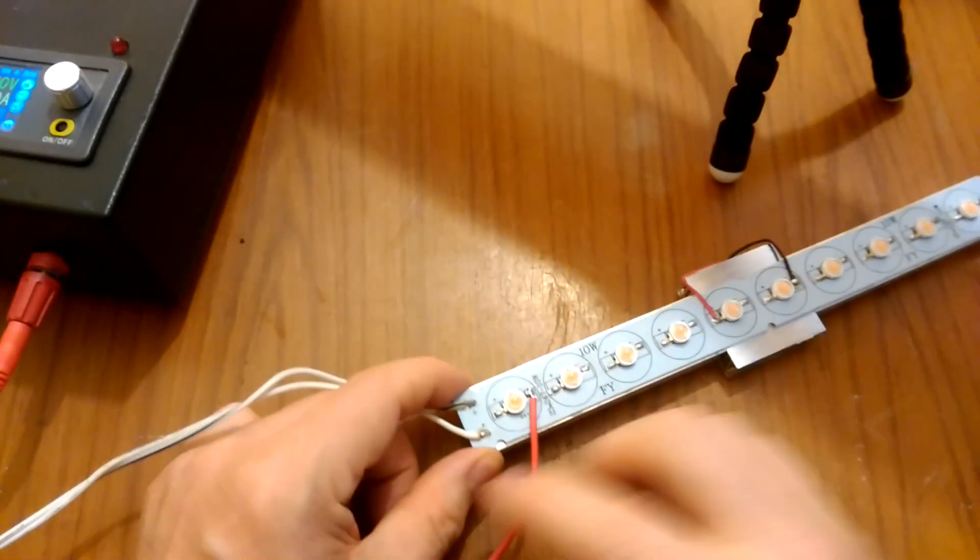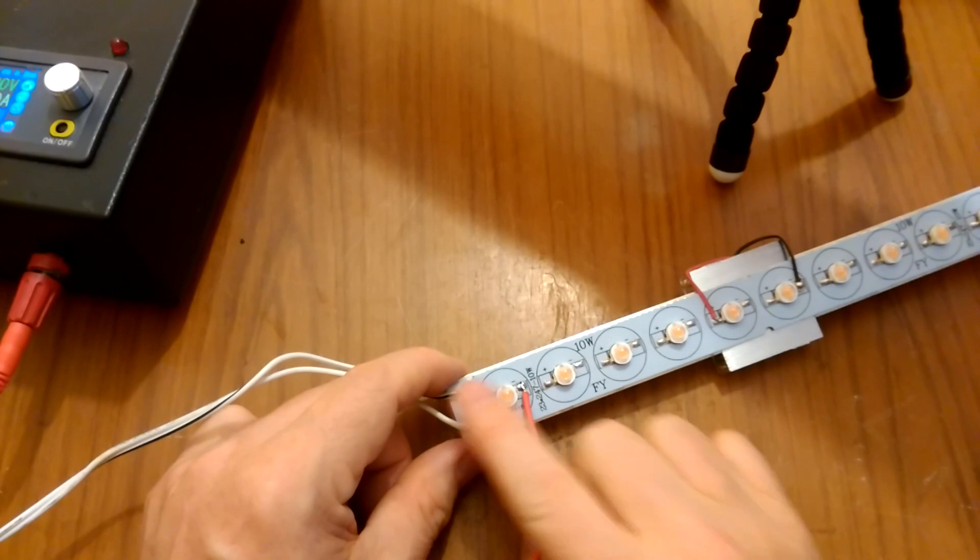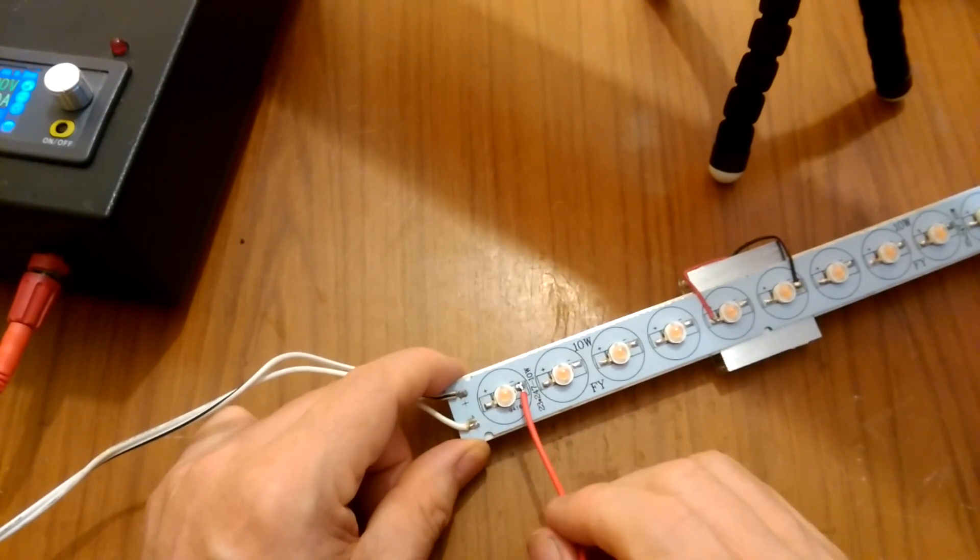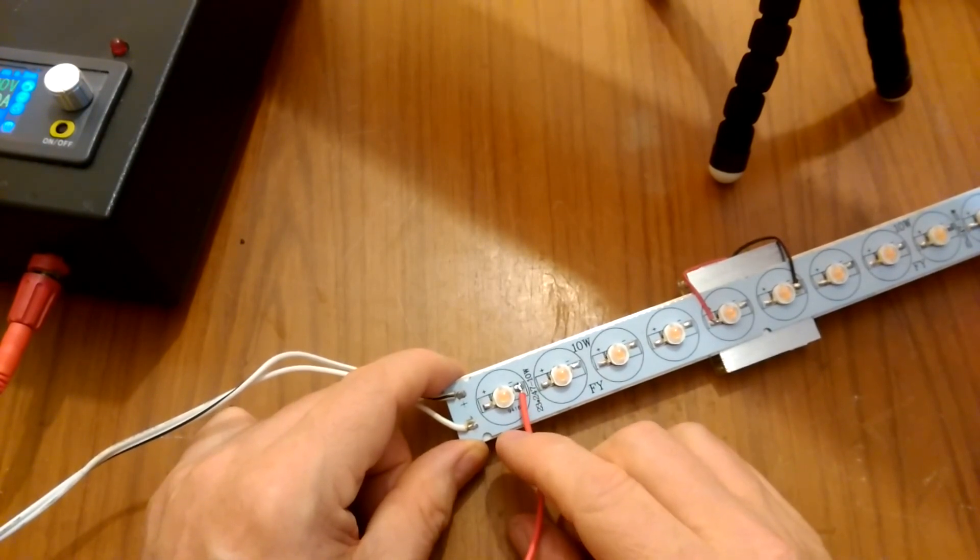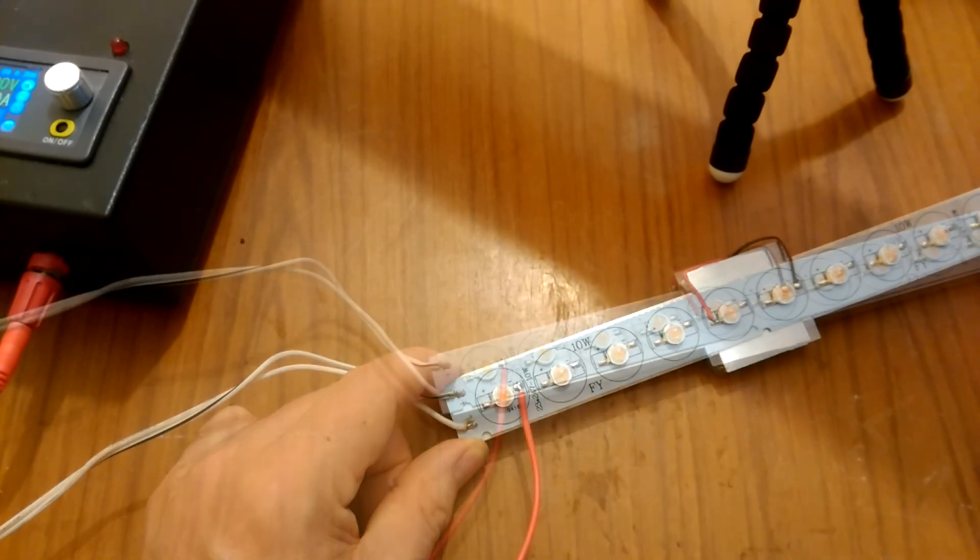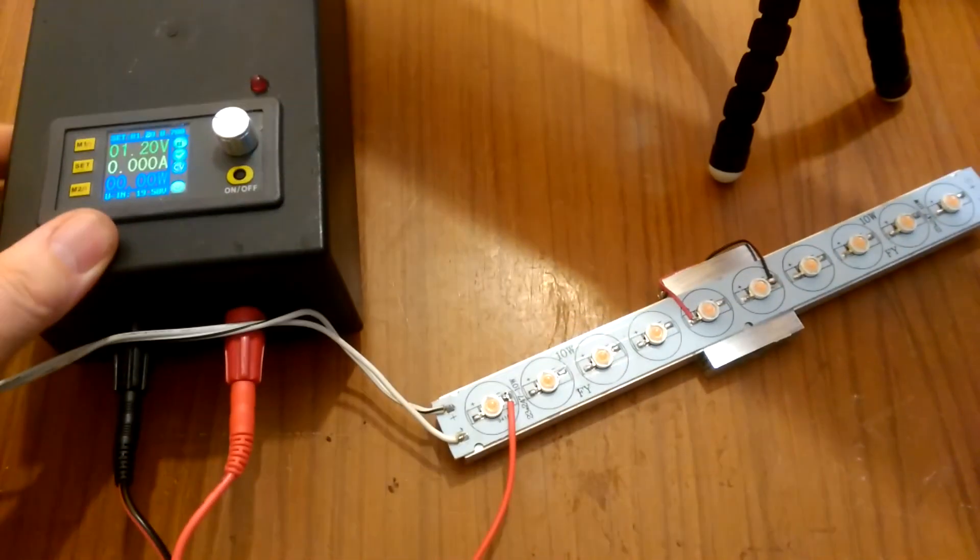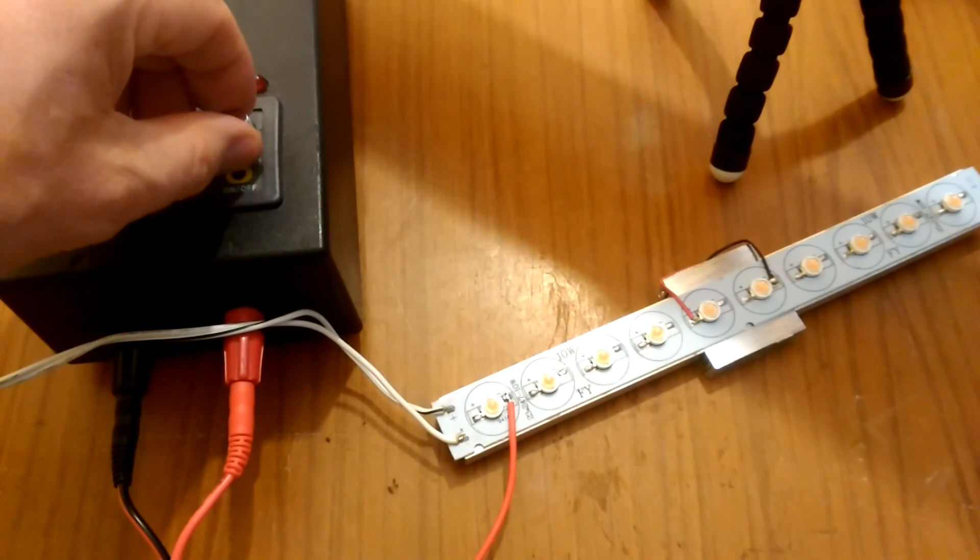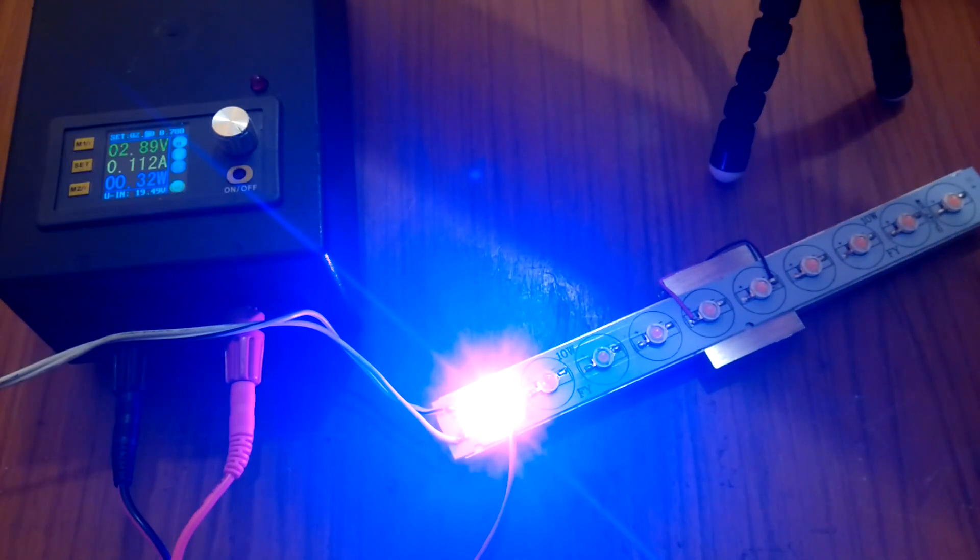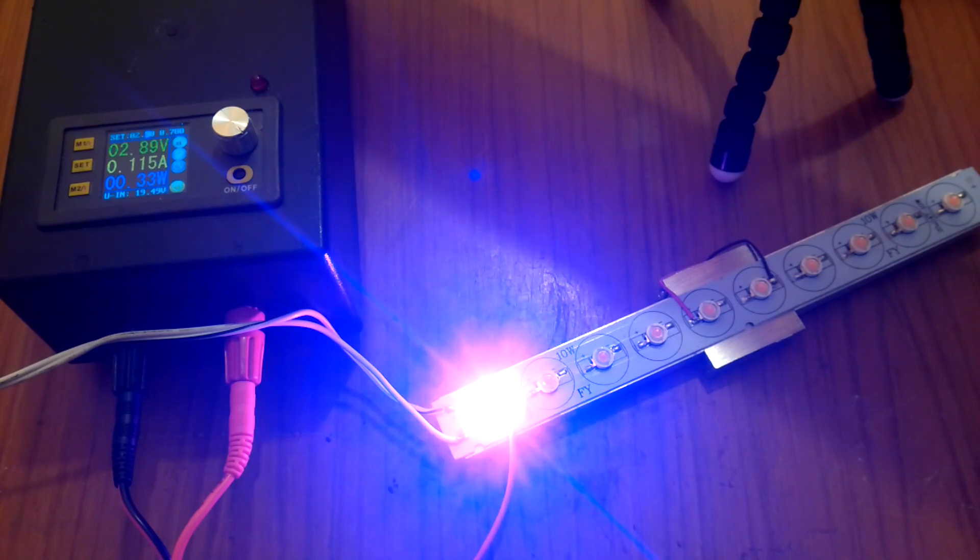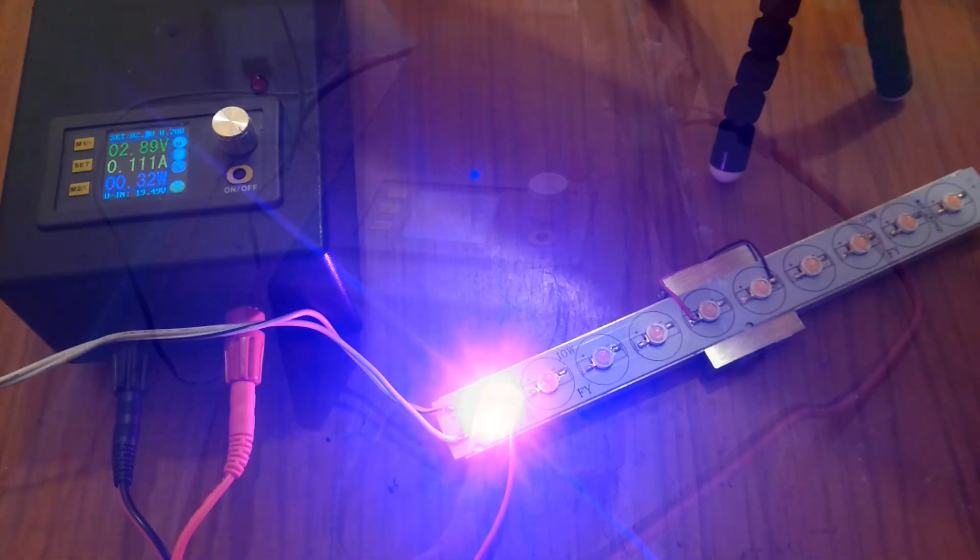My bench power supply won't run this unit, it doesn't go high enough in voltage, so I've added this jumper so I can just run one LED. That's not normally necessary for testing LEDs. So we'll turn the voltage up until the LED comes on. I've set the limit of current to 750 milliamps and the LED is going. We'll take the spectrum.